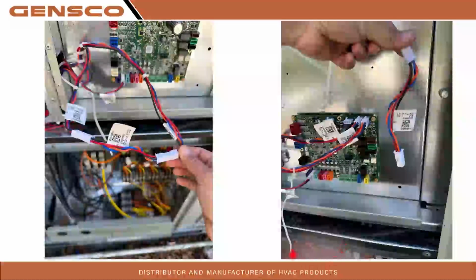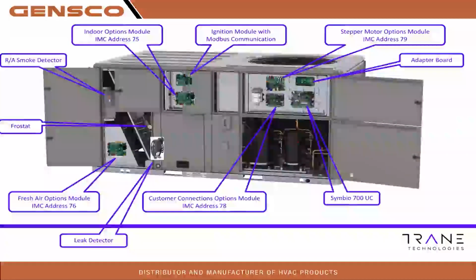So you're going to wire up your electric heat kit. You're going to come up here and you're going to land it right here. What I've seen quite a few times now, I don't know if they didn't open the panel, they didn't have the board at first or whatnot. This electric heat gets installed. They see this connection, because remember, this is the same board. It's just addressed differently to tell it different functions. They ran over, plugged the heat strip into these connections. So I've seen it a couple times. Just be aware of it. Your heat strip runs up into the indoor options module.